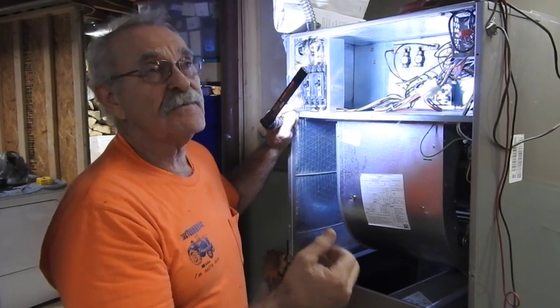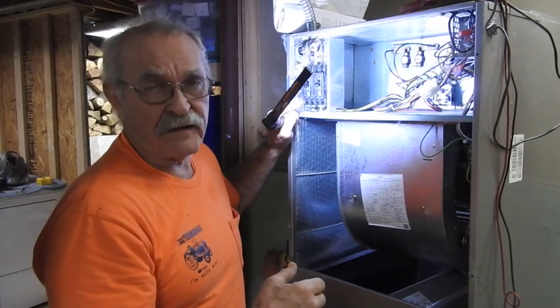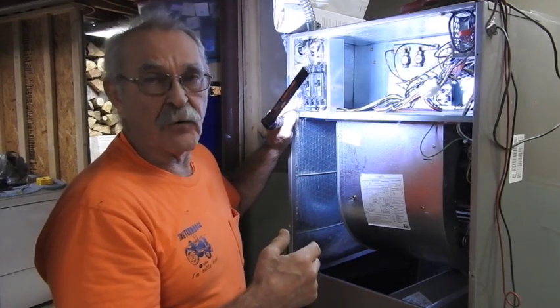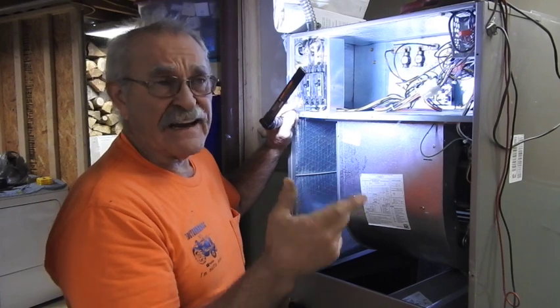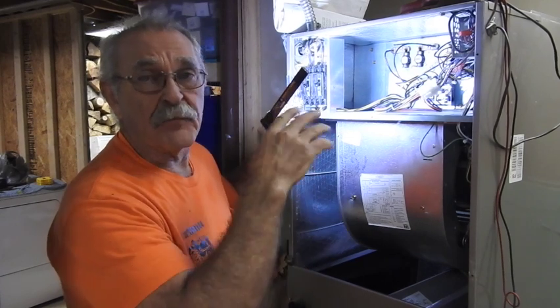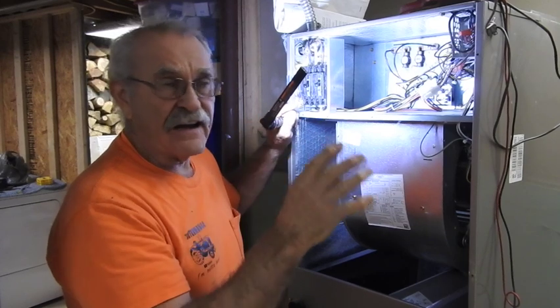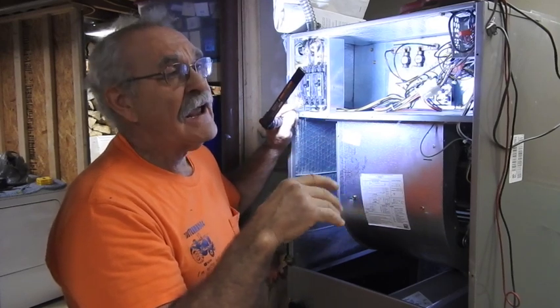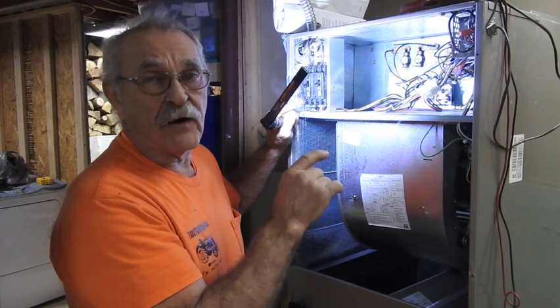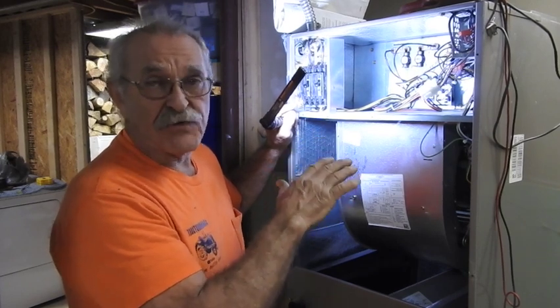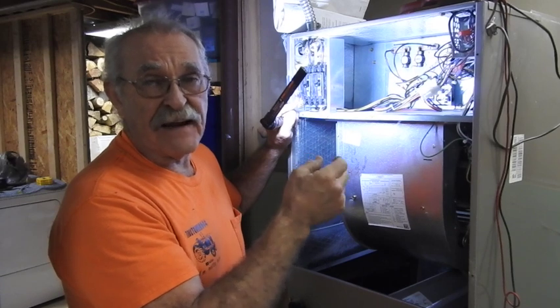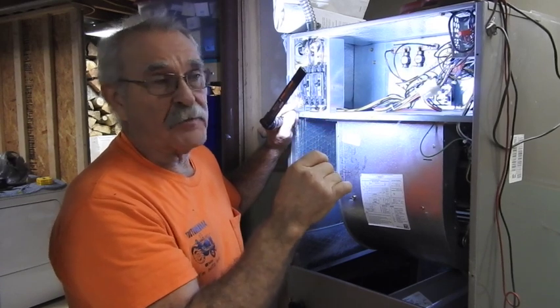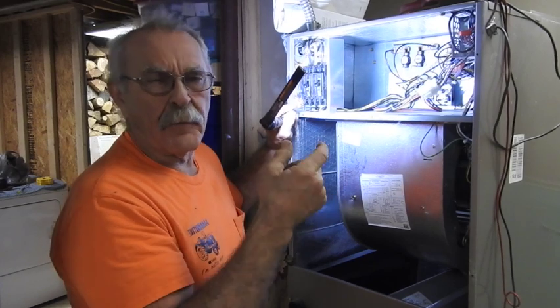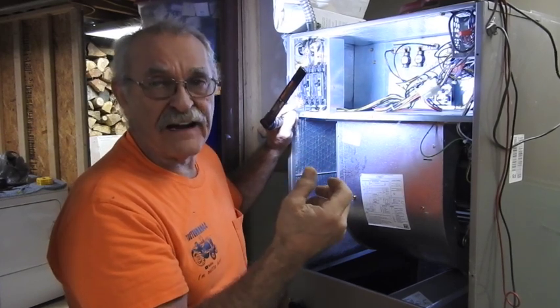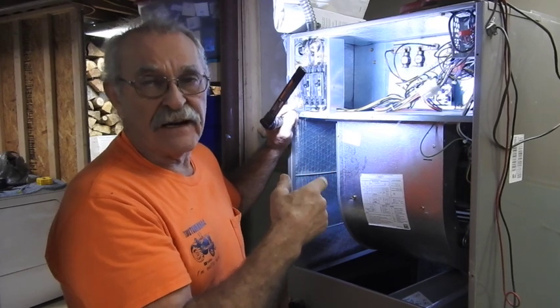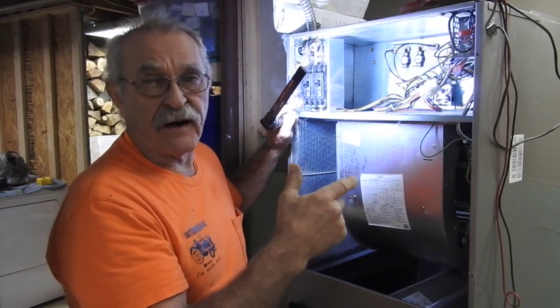But it's a fairly large system, and it was an extremely complicated duct network, and there just was not enough heat getting to where it needs to go. This is the tail end of a project where we've isolated the attic, put in a complete separate system, totally renovated the entire duct system down here on the first floor, and we're putting the capacity in the ductwork to be adjusted to where they can use the downstairs finished off area as a living space or not, by means of moving mechanical dampers. So what we're doing, we're going back in with a properly sized air handler for the 15 kW new strip heat that's going into the new furnace, matched with a new smaller air conditioning.